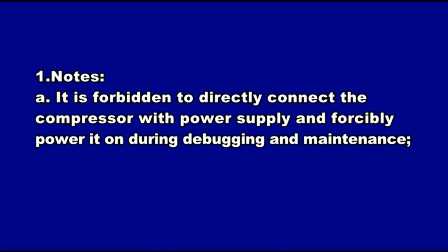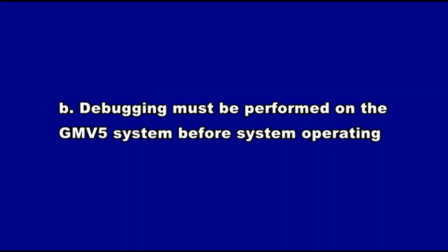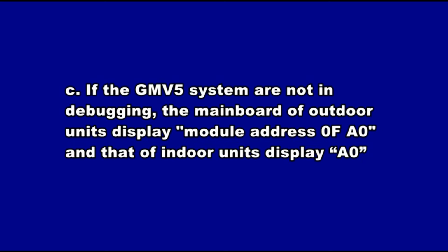Unit commissioning. Notes: it is forbidden to directly connect the compressor with power supply and forcibly power it on during debugging and maintenance. Debugging must be performed on the GMV5 system before operating. If the GMV5 system is not in debugging, the main board of outdoor units displays module address 0FA0 and that of indoor units displays A0.